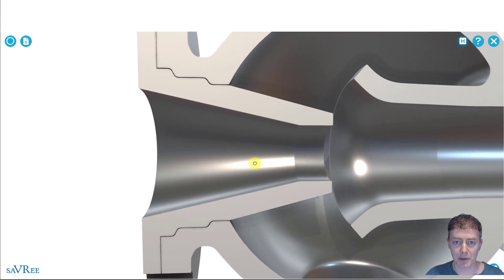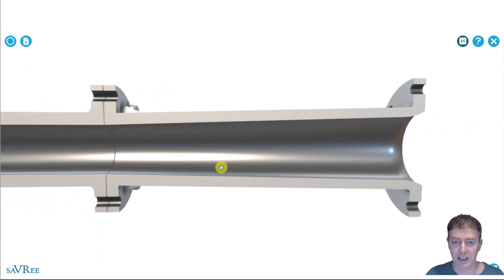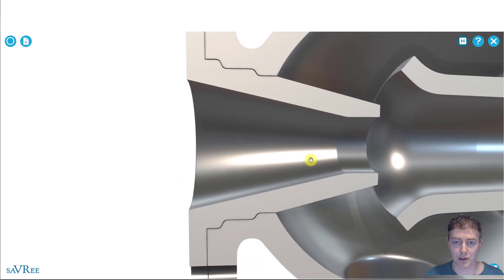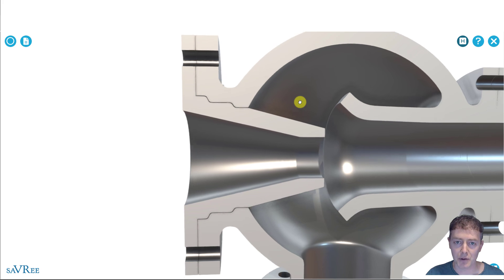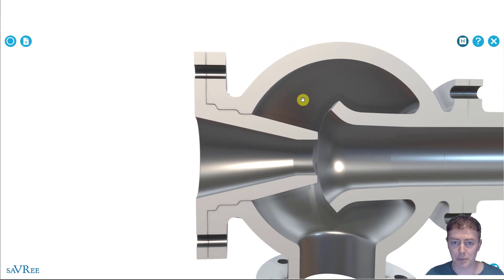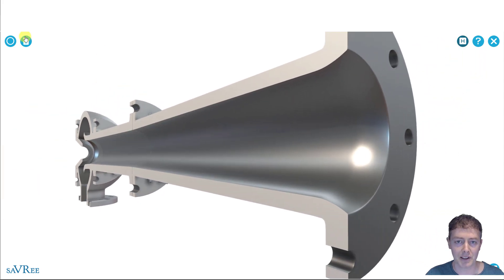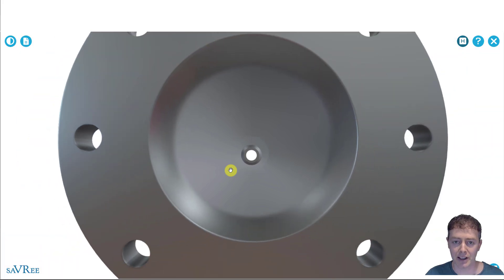Our eductor has motive fluid coming in here. It flows through the nozzle and the nozzle converges. The geometries throughout this eductor are very important — notice here: gradually getting wider, fixed or constant diameter, slightly converging, and a nozzle that converges. You'll hear people say it's because of Bernoulli's principle, but it's much more accurate to say this eductor is using what's called the Venturi effect. The Venturi effect is like Bernoulli's principle, but limited to where the flow path of a fluid is within constrained limits — the constraint here is the pipe diameter, the piping itself, the eductor body.